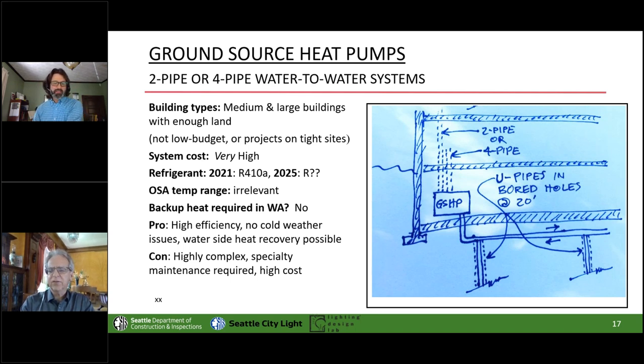So we did one of these at the Shulshul Marina, and we did about 3/4 of the capacity, and then we have a little backup boiler for the coldest of cold days. And what was neat about Shulshul is that the water's coming down off the hill, so it doesn't matter that the load isn't balanced and there's no cooling, because the water is always moving heat in underground. The underground water movement is such that it's recharging the well constantly. So there's something to be aware of there.